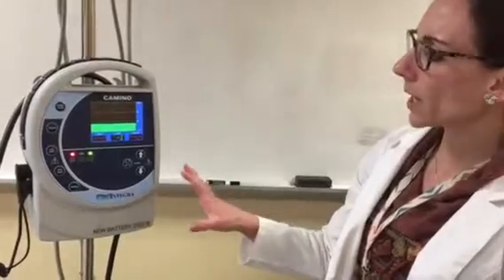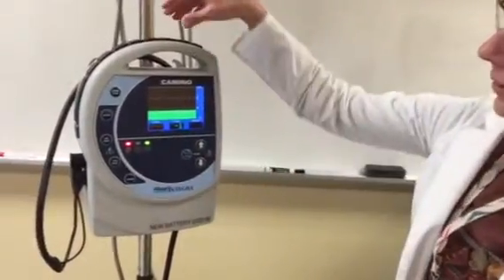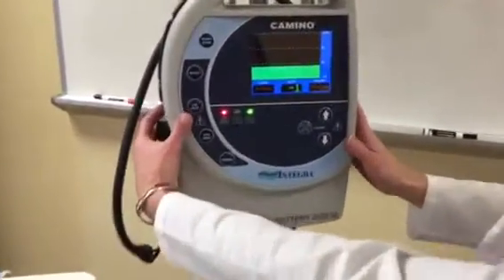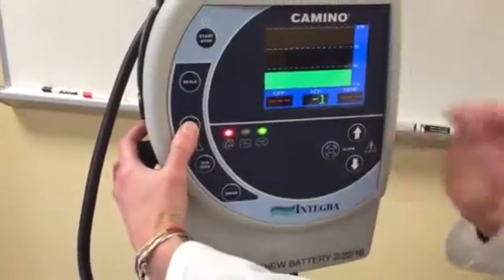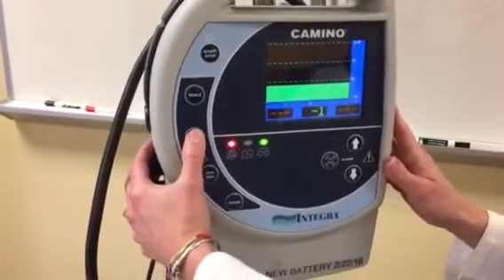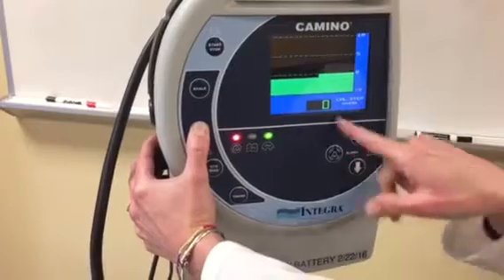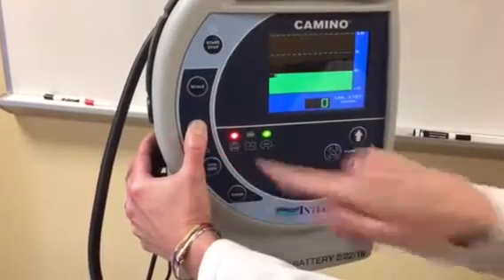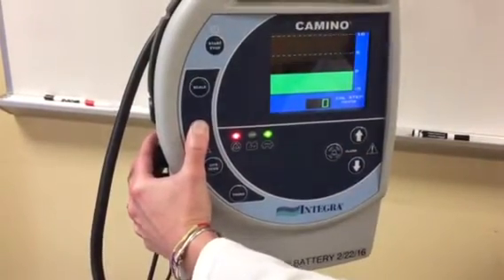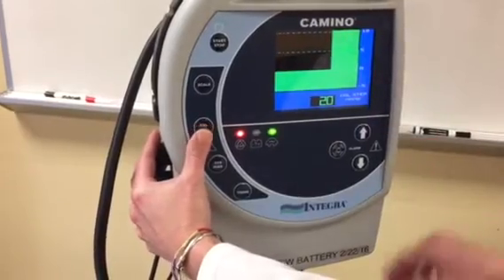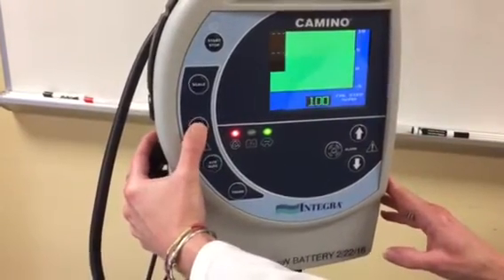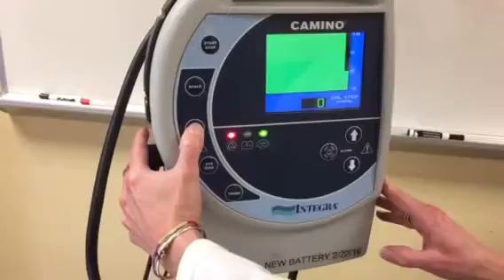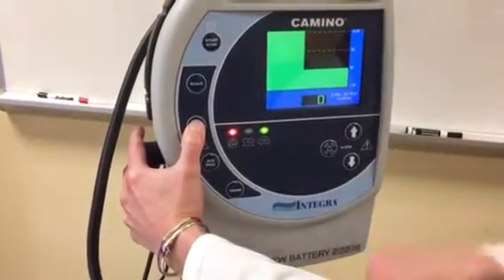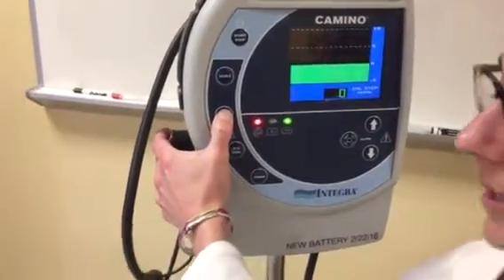But for calibrating for the first time around, you'll come in here to your Camino and you'll push cal step until the ICP reads 0. So normally just pressing it once will get you to 0. You need to hold it down while it's reading 0. If you inadvertently push it too many times, it's going to keep going. Then you have to cycle up past 200 and get to 0 again. Hold it.